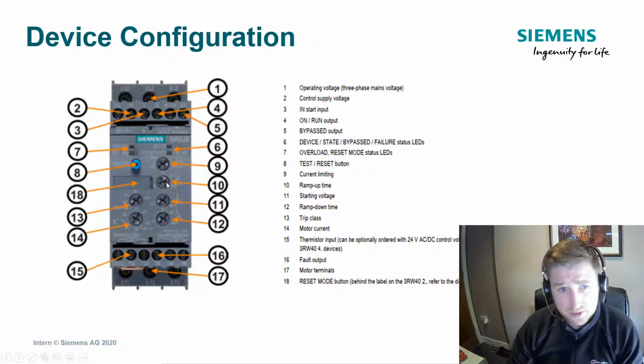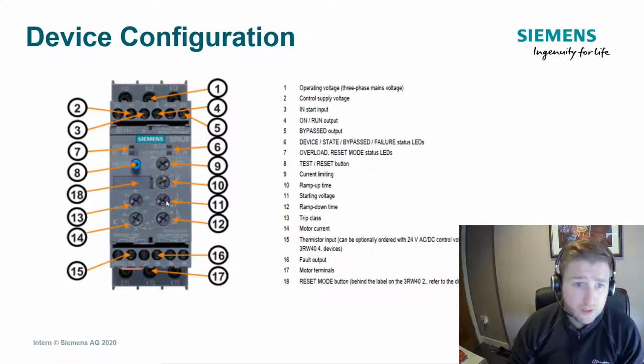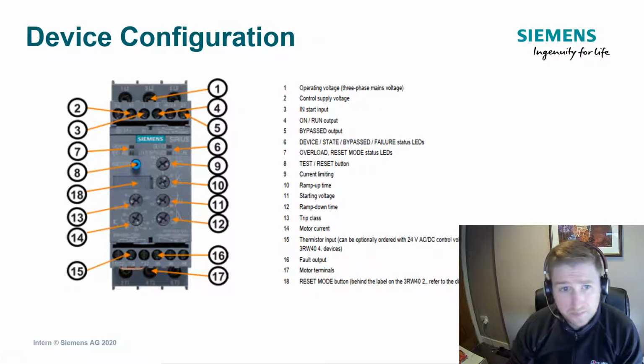So if you want to use voltage control as opposed to current control, you would turn this potentiometer to the full amount, and then you would use this voltage ramp up time to effectively control the voltage up to the full line voltage. Here with pot 11, this also gives you a pedestal voltage. So the pedestal voltage is what voltage you want the application to start at. So if you had a 400 volt application and you set that pot to 50%, then it would take X amount of time, from what you've set this potentiometer to for the ramp up, to reach the full line voltage.